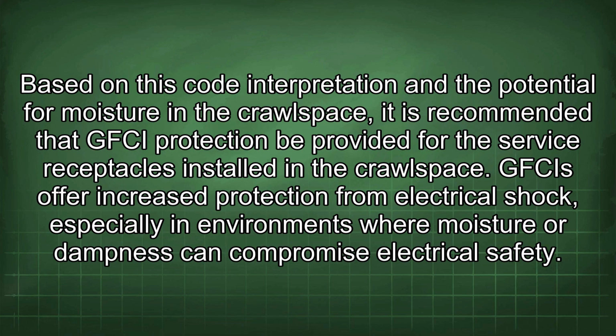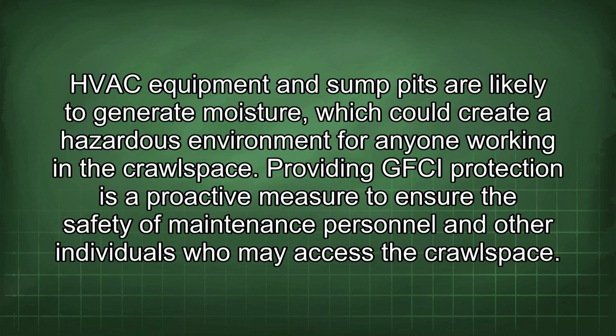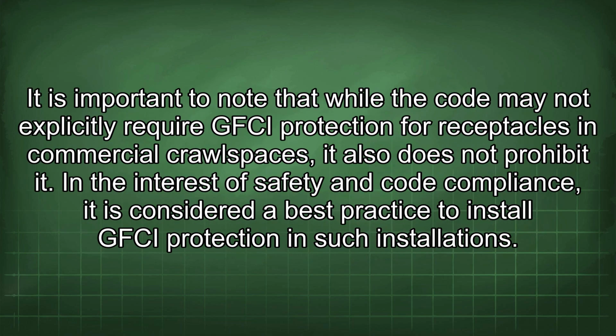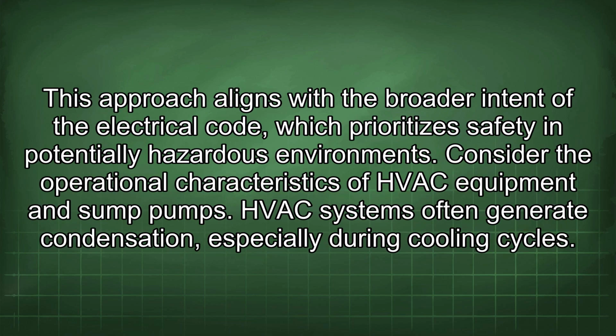GFCIs offer increased protection from electrical shock, especially in environments where moisture or dampness can compromise electrical safety. HVAC equipment and sump pits are likely to generate moisture, which could create a hazardous environment for anyone working in the crawlspace. Providing GFCI protection is a proactive measure to ensure the safety of maintenance personnel and other individuals who may access the crawlspace. It is important to note that while the code may not explicitly require GFCI protection for receptacles in commercial crawlspaces, it also does not prohibit it. In the interest of safety and code compliance, it is considered a best practice to install GFCI protection in such installations. This approach aligns with the broader intent of the electrical code, which prioritizes safety in potentially hazardous environments.